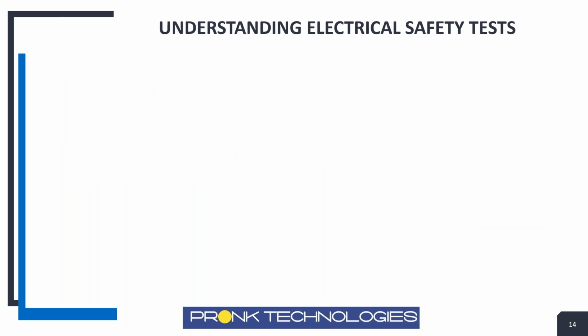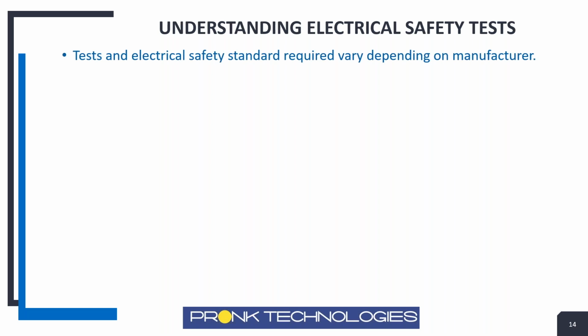So that's general information on one of the most critical tests on the defibrillator analyzer, for delivery of energy for discharge and for pacing. The other thing that's very interesting, at least to me, but I'm kind of a tech geek, so maybe I'm a little over the top, is some of the requirements for the testing in reference to electrical safety testing. There are different safety standards you are required to follow depending on the defibrillator. If you're following the manufacturer's specifications in their service manual, you've got to do what they say in their service manual. Now, some organizations do NFPA across the board on all devices, which honestly makes it much more straightforward.